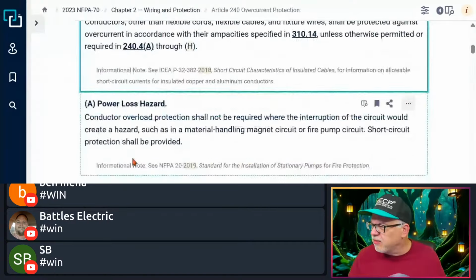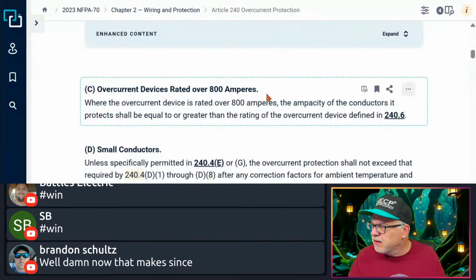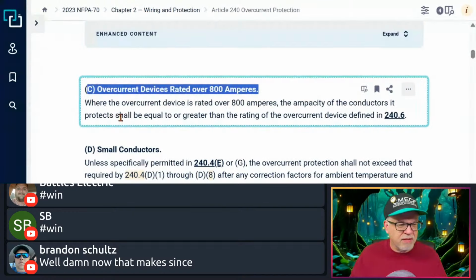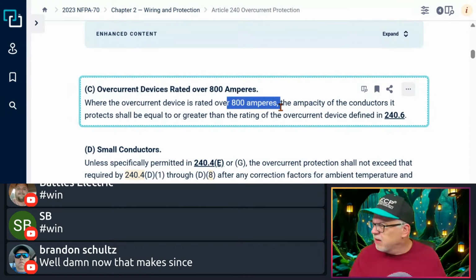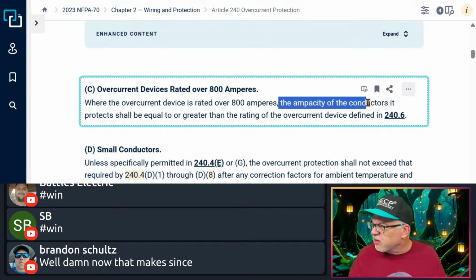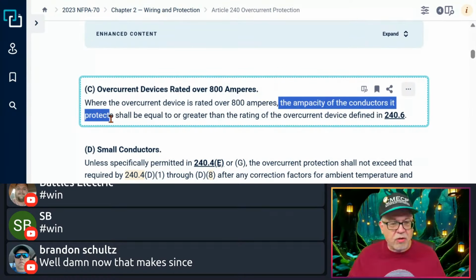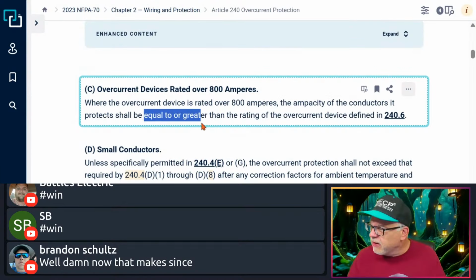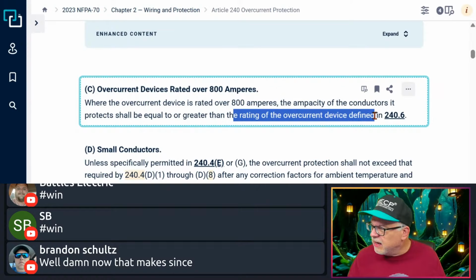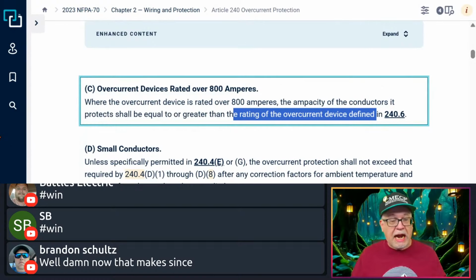And we're looking at C, overcurrent protection, right? It says where the overcurrent device is rated over 800 amps, the ampacity of the conductors it protects, so on the load side of it, shall be equal to or greater than the rating of the overcurrent protective device in 240.6. So I have to make sure that I have conductors that can handle that 1200 amps.